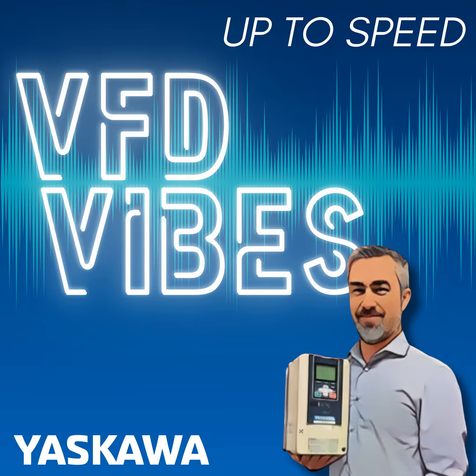You brought up another point. Using the drive in itself does bring a lot of efficiencies, as we actually talked about in our last episode together. But doing the bare minimum doesn't necessarily make the drive run as efficiently as it possibly could. So when we're trying to squeeze all of the power out of every amp that we're putting in there, auto tune is a great place to start. And that's a really important thing to do when we're all trying to save money, save the environment, reduce energy.